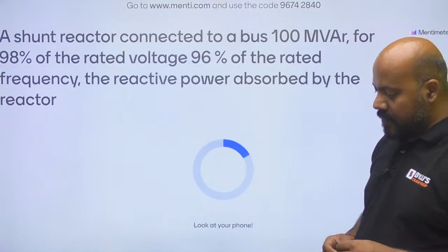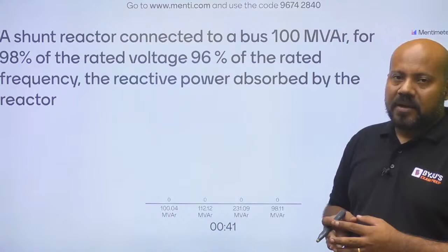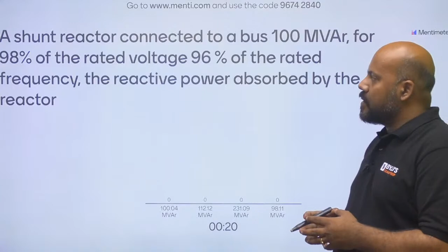Now, this is again a very interesting question related to the reactive power absorbed by the shunt reactor based on your reactive power compensation. You have to relate the reactive power absorbed by the reactor in terms of the voltage and the frequency. You know how to relate it. And he is saying the voltage and the frequency changes are mentioned. Voltage has become 98% of the rated voltage and frequency has become 96% of the rated frequency. And you have to give what is the reactive power absorbed by the reactor in case of the changed voltage and frequency case.